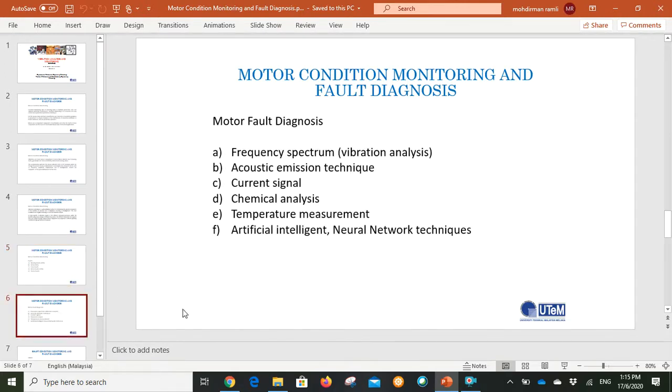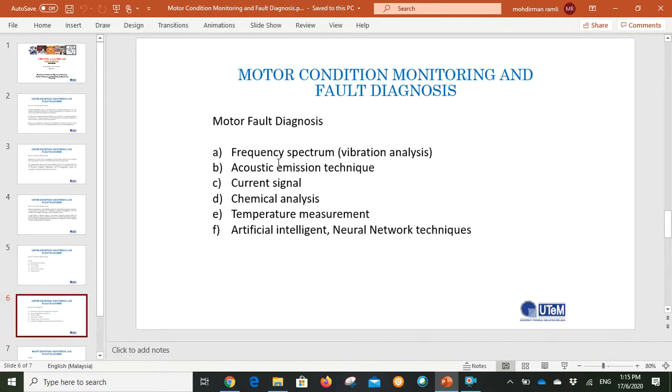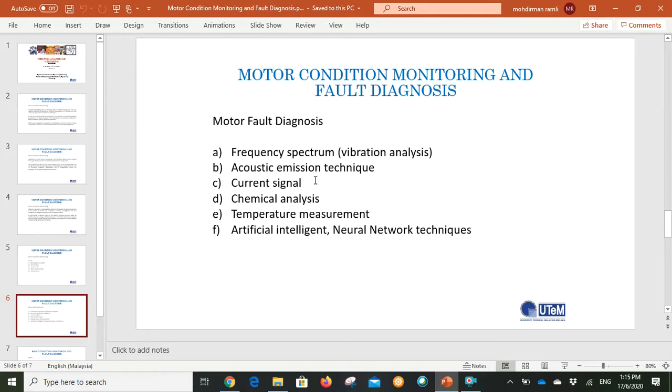To implement motor fault diagnosis, as shown here, there are various techniques. Among these techniques is vibrational analysis which focuses on frequency spectrum. Another is acoustic emission technique, which is generated by sudden release of energy caused by material deformation. Or using current signal technique which focuses on the bearing condition inside the motor and focuses on magnetic flux density inside the motor.